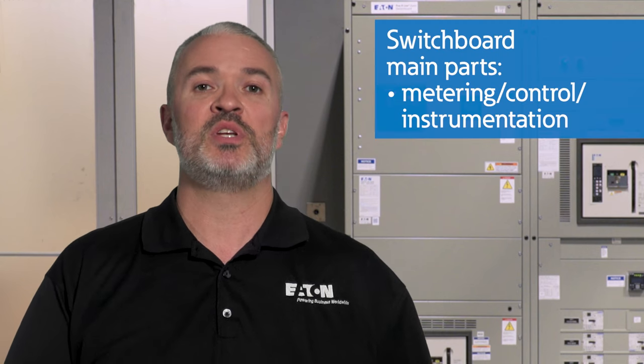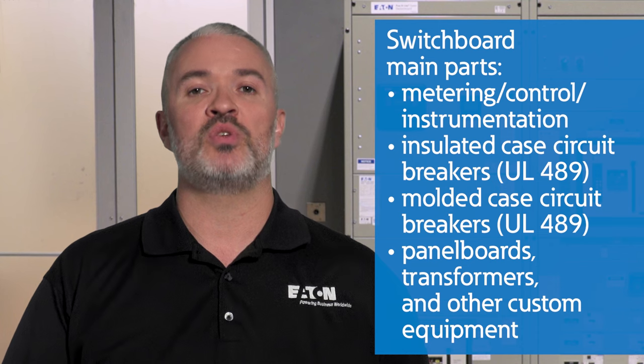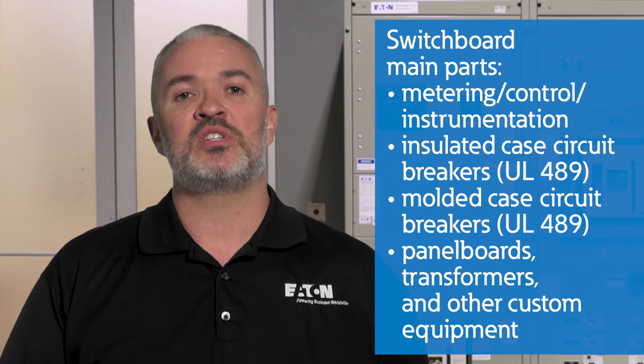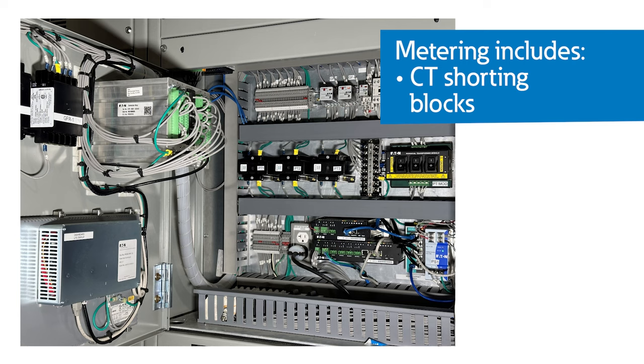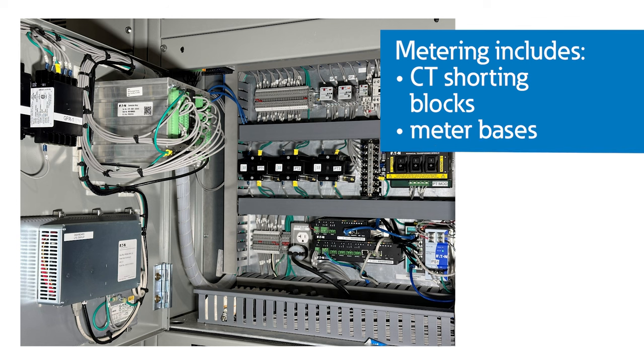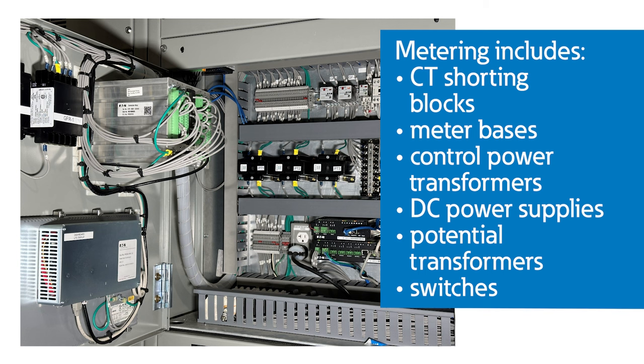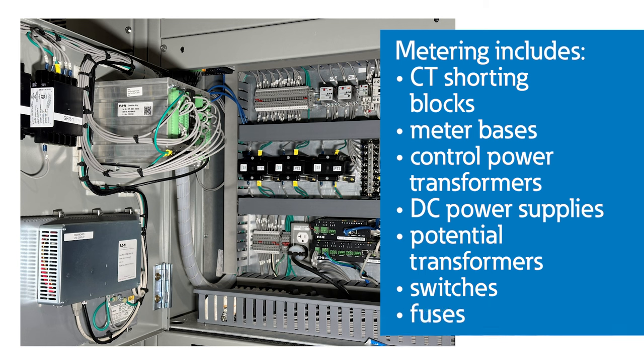Now let's discuss the main parts of a typical switchboard: metering, control and instrumentation, insulated case circuit breakers, molded case circuit breakers or MCCBs, and panel boards, transformers, and other custom equipment. The metering section includes CT shorting blocks, meter bases, control power transformers, DC power supplies, potential transformers, switches, fuses, and much more.